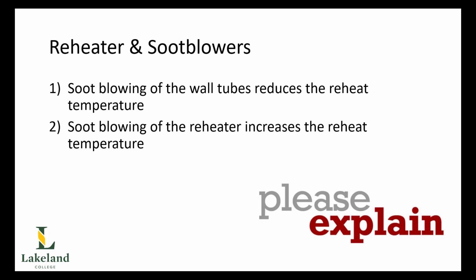Now, there's a point to note regarding the radiant wall soot blowing, and I'm almost hearing a few of you think this with your internal cogs ticking over. And the thought would go something like this. You said earlier that when we increase the firing rate of our boiler, then the radiant superheater temperature would go down, i.e. a falling steam temperature characteristic. So why doesn't that happen here in number 1 when we soot blow the radiant walls? Good question. The answer is, where in that statement for number 1 did it say I was increasing the firing rate? It didn't. So that's what we're assuming.